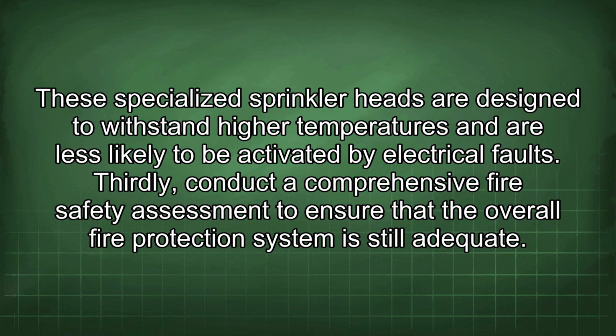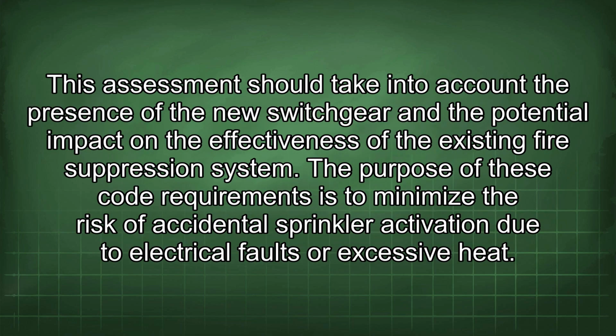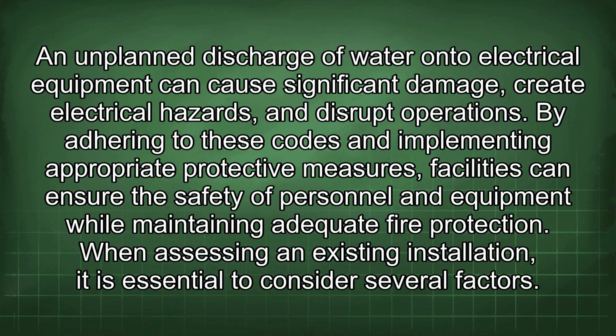Thirdly, conduct a comprehensive fire safety assessment to ensure that the overall fire protection system is still adequate. This assessment should take into account the presence of the new switchgear and the potential impact on the effectiveness of the existing fire suppression system. The purpose of these code requirements is to minimize the risk of accidental sprinkler activation due to electrical faults or excessive heat. An unplanned discharge of water onto electrical equipment can cause significant damage, create electrical hazards, and disrupt operations.